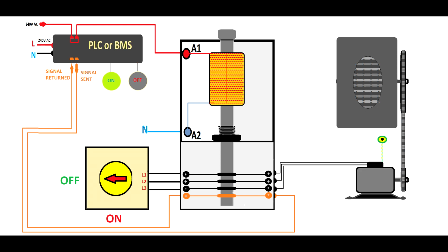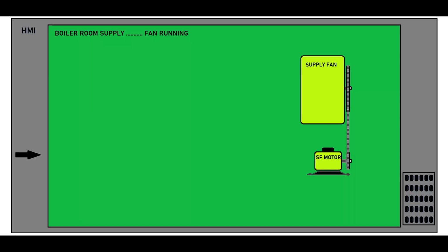One of the bad things in this situation is that if you turn off the isolating switch, you will still have the signal back into the programmable logic control, and the programmable logic control will tell the HMI that the fan is running. This is a bad integration, and on many occasions I have had to drive hundreds of miles just to figure out that someone turned off the switch.